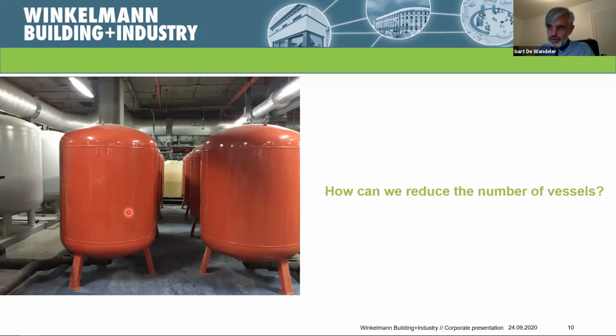But that also means that the complete contents of the water reserve are not fully fitted for your installation. So those are really quite critical points, also for afterwards looking at degassing, corrosion, and heat transfer. The consumption of your heat or cooling machine is all related to the setup of a water reserve in an expansion tank. So this is today at least more important than before.